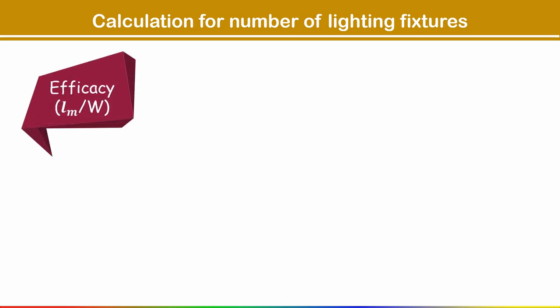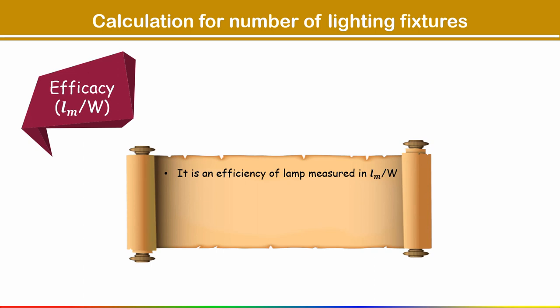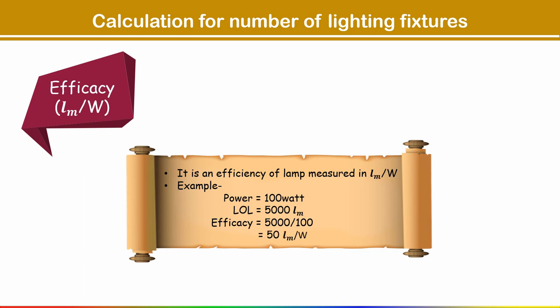Next is efficacy. It is the efficiency of a lamp measured in lumens per watt. The lumens value you will get from the manufacturer of the lamp. For example, if a lighting fixture has a power value of 100 watts and lumens of lamp is 5000, then efficacy equals 5000 divided by 100, which is 50 lumens per watt.